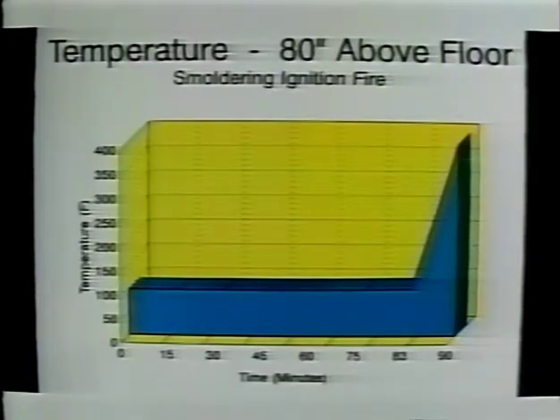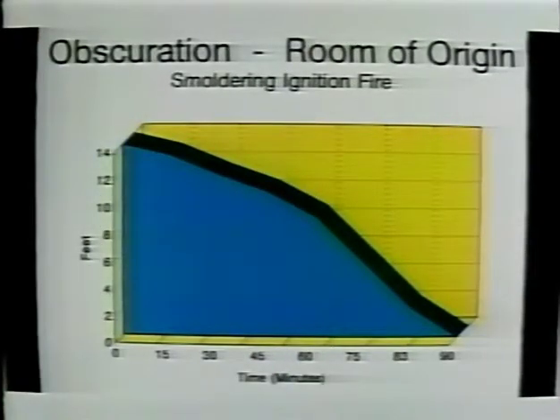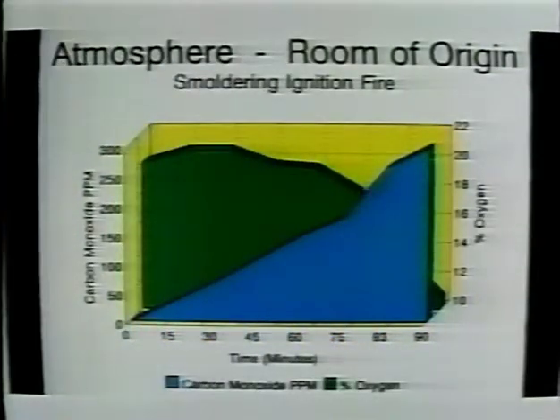The graph represents the temperatures in the room of origin. There was a constant rate of smoke generation, which in turn decreased the visibility in the room of origin. Very little decrease in oxygen level was experienced in the room of origin until the time of ignition. As oxygen was consumed by the combustion process, the level decreased rapidly. The parts per million of carbon monoxide increased slowly up to the point of ignition, at which time the level of carbon monoxide increased rapidly.